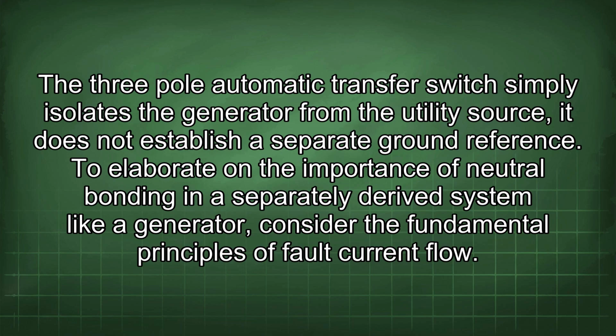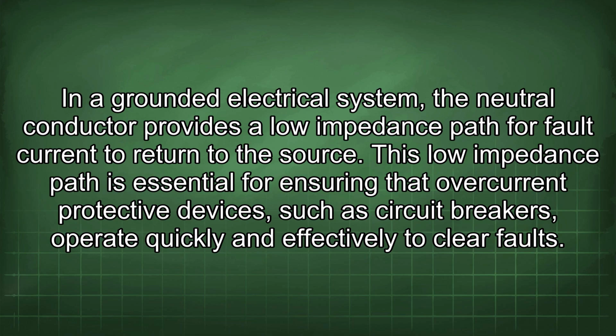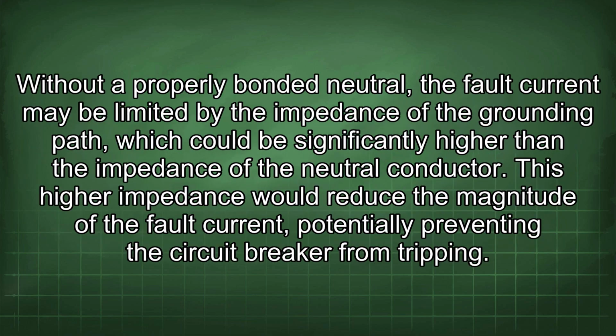To elaborate on the importance of neutral bonding in a separately derived system like a generator, consider the fundamental principles of fault current flow. In a grounded electrical system, the neutral conductor provides a low impedance path for fault current to return to the source. This low impedance path is essential for ensuring that overcurrent protective devices, such as circuit breakers, operate quickly and effectively to clear faults. Without a properly bonded neutral, the fault current may be limited by the impedance of the grounding path, which could be significantly higher than the impedance of the neutral conductor. This higher impedance would reduce the magnitude of the fault current, potentially preventing the circuit breaker from tripping.